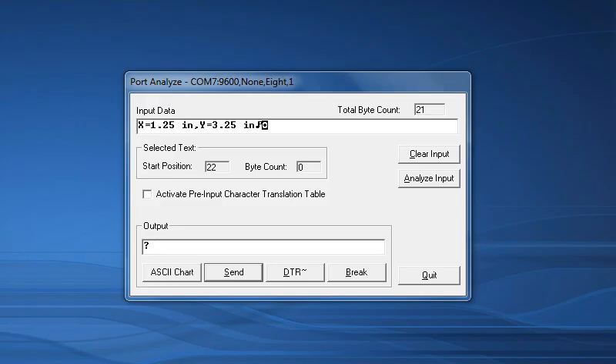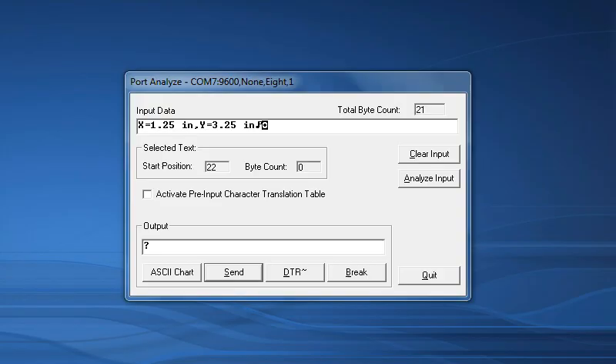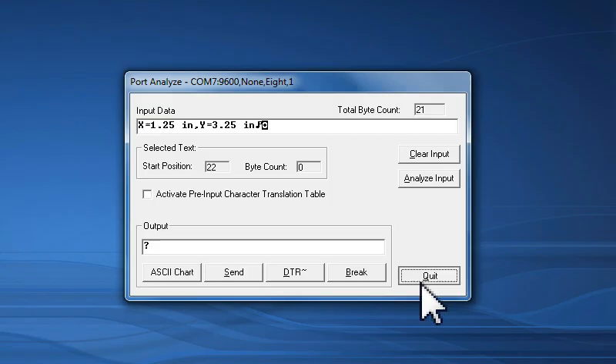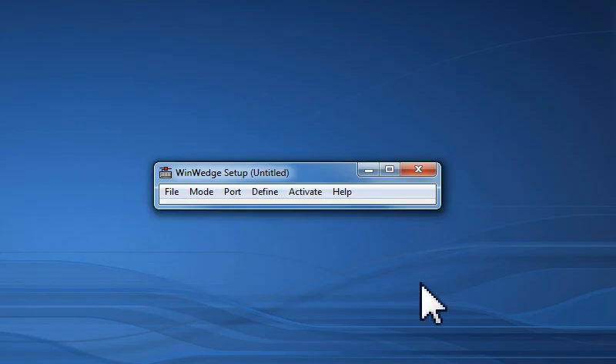When I examine the data that the device sends, I can see that it transmits two values, separated by commas, with X and Y labels, and the units for each value. At the end of the data, I also see two additional characters. The musical note is a carriage return, and the box with a circle in it is a line feed character. Carriage returns and line feeds are commonly used to indicate the end of a string of data. Now that I know everything is working the way it should, and I also have a good understanding of how the data from my instrument is structured, I can close the Analyze window and continue configuring WinWedge to feed the data onto Excel.